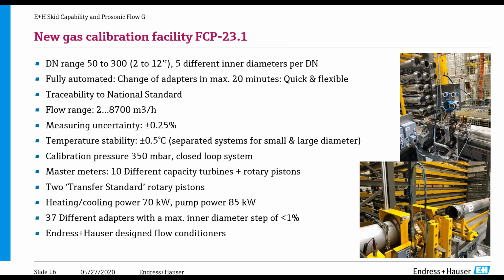Now, I mentioned earlier, we flow calibrate every single meter in-house. We don't do this externally, so this improves our delivery situation and also our cost position. We have several calibration rigs, but we had to build a new one for this particular device. It goes from 2 to 12 inch. For the smaller ones, we calibrate on a different gas calibration rig that we have in-house. We can do a flow range from 2 meters cubed per hour up to 8,700. More or less, the high end of the rig right now is 40 meters per second.